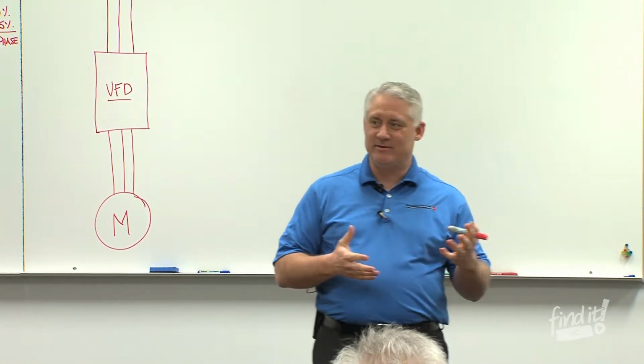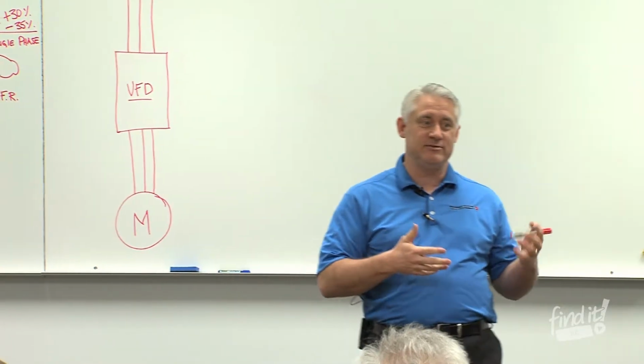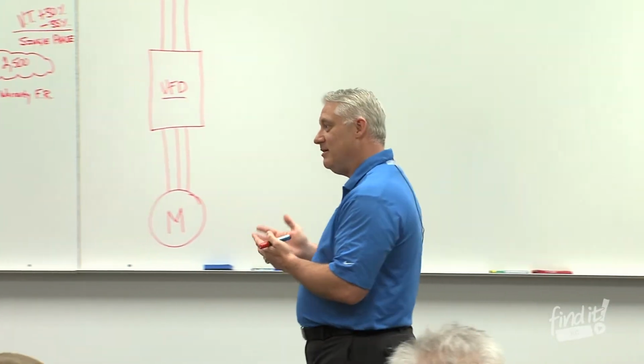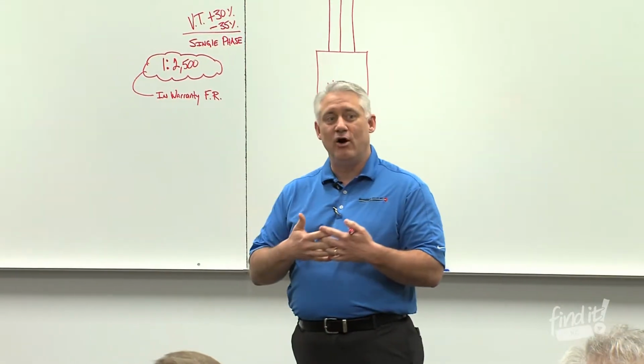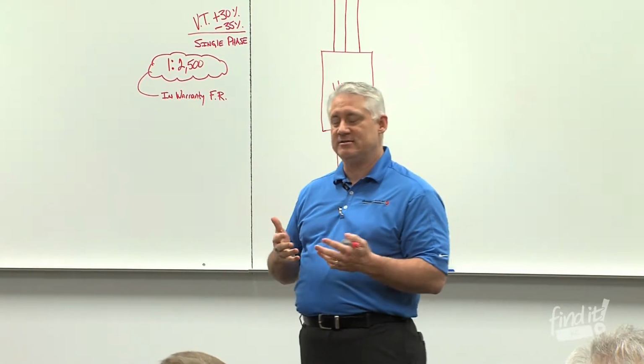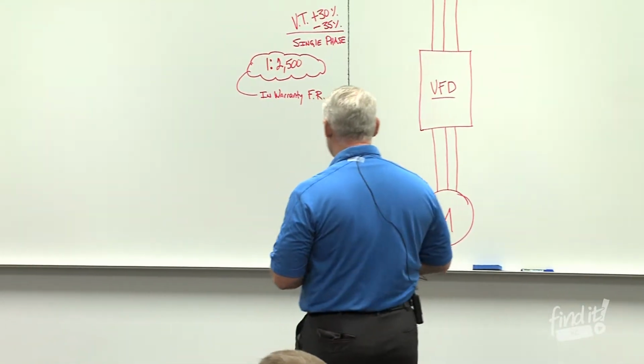And I'll get into why that is. We're adding components, we're adding points of failure. So if the drive's very, very good and is unlikely to fail and you don't have an ultra critical application, does it really make sense to have a bypass? So we'll start with that.